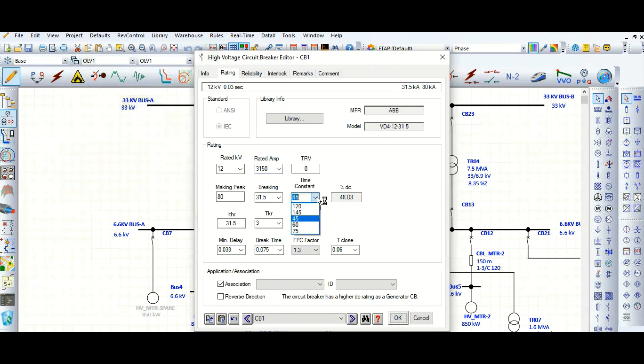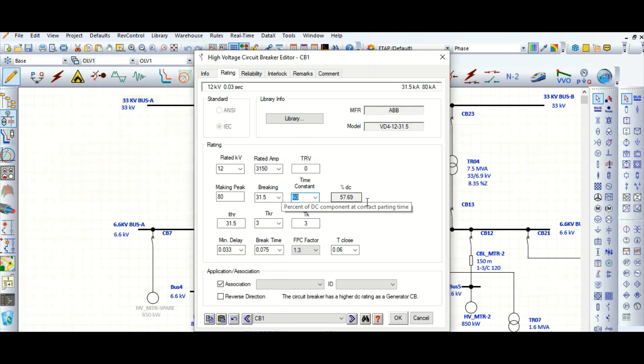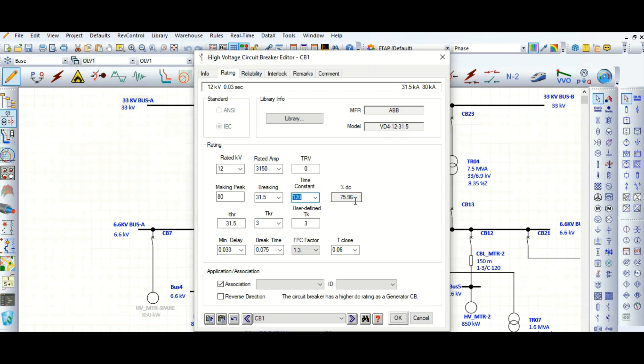Here is the time constant. You can choose whether 45 milliseconds or 60 milliseconds — I will select 60 milliseconds. For 45 ms, the percentage DC component is 48.03%. If you select 60 ms time constant, the percentage DC value changes to 57.69%.